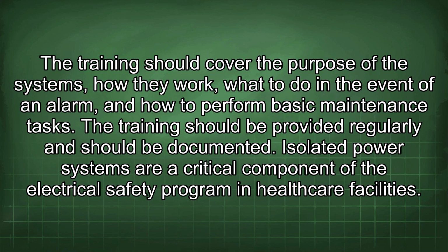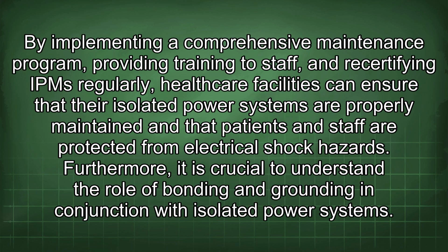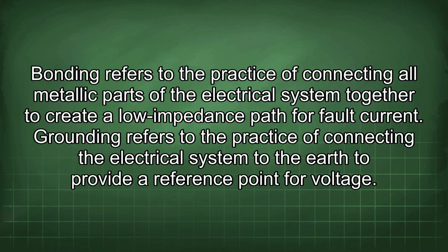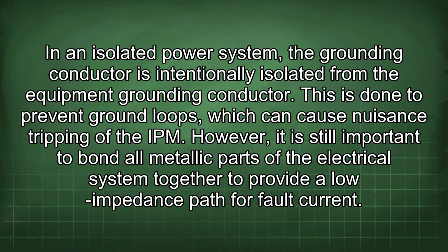Isolated power systems are a critical component of the electrical safety program in healthcare facilities. By implementing a comprehensive maintenance program, providing training to staff, and recertifying IPM regularly, healthcare facilities can ensure that their isolated power systems are properly maintained and that patients and staff are protected from electrical shock hazards. Furthermore, it is crucial to understand the role of bonding and grounding in conjunction with isolated power systems. Bonding refers to the practice of connecting all metallic parts of the electrical system together to create a low impedance path for fault current. Grounding refers to the practice of connecting the electrical system to the earth to provide a reference point for voltage. In an isolated power system, the grounding conductor is intentionally isolated from the equipment grounding conductor.